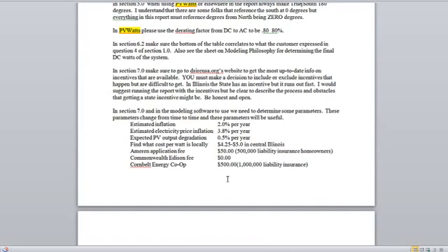Expected PV degradation, only a half a percentage per year. Find out what local costs are. As a site assessor, you must not put any sort of data inside of that thing that tells what specific pieces of equipment you're going to use. But on the other hand, you as a site assessor really need to know what local trends are. Currently, right now in central Illinois, for a residential install, a very rough sketch seems to be shaping up right now in the early part of 2014 as being $4.25 a watt installed. Know what the application fees are. I put those here.